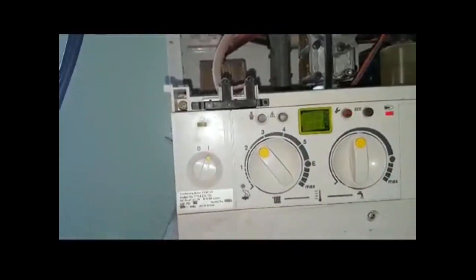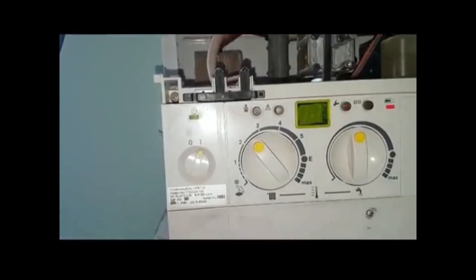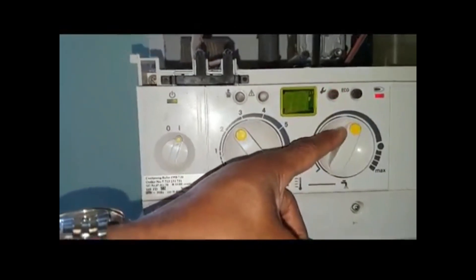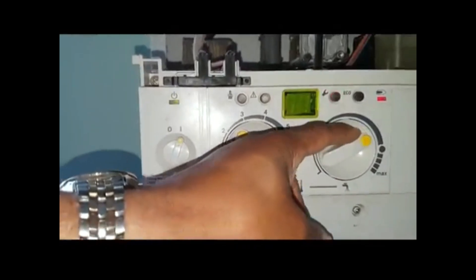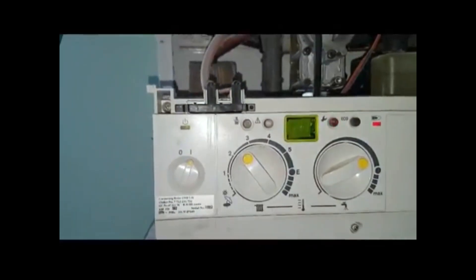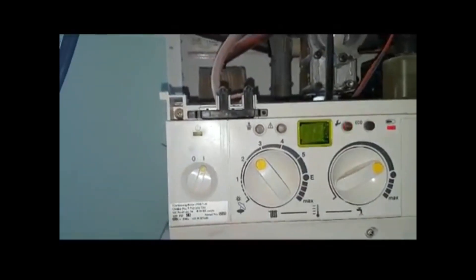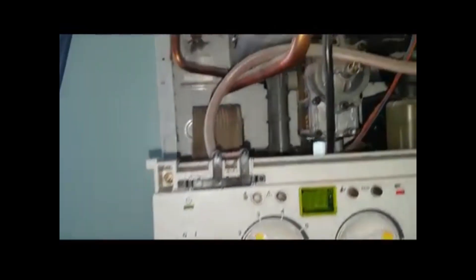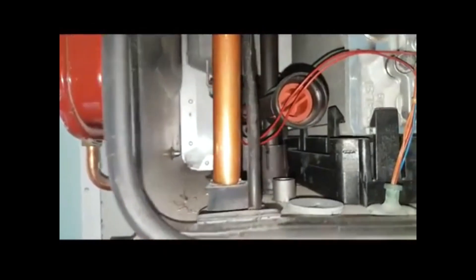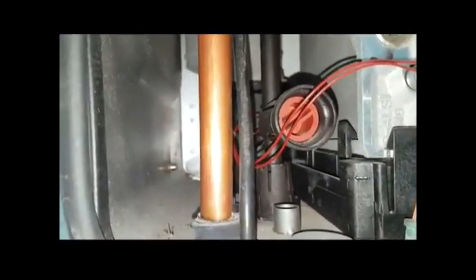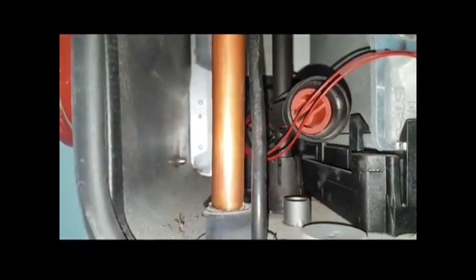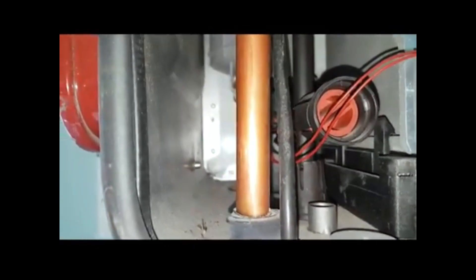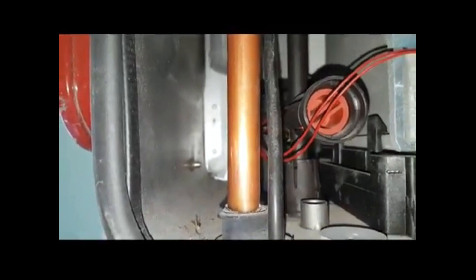Now once you've done that and that's okay, you now move this hot water control knob to go to 2. That now is maximum setting fan speed. And then you adjust the gas, and that reduces the maximum CO2 which is supposed to be 9.2.